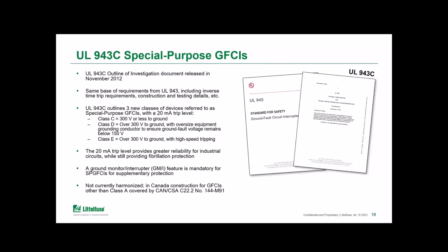And Class E, that's also for circuits above the 300 volts line to ground. The difference being Class D requires an oversized grounding conductor to make sure we're keeping a low touch voltage on the frame of equipment. So these special purpose GFCIs have a trip level of 20 milliamps. And as they're used on industrial equipment, this slightly higher trip level helps to ensure reliability. Now, in exchange for moving this trip level upwards, UL added another new requirement called a ground monitor interrupter. And this is a function that checks the continuity of the equipment grounding conductor to be sure there is a valid low resistance path before the load can be energized.